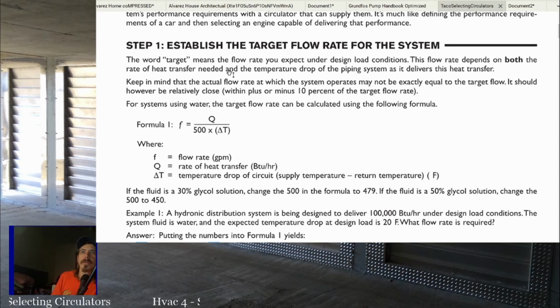All right, so the target is the flow rate you'll expect under design load conditions. The flow rate depends on both the rate of heat transfer needed and the temperature drop of the piping system as it delivers this heat transfer. Keep in mind the actual flow rate at which the system operates may not be exactly equal to the target flow. It should, however, be relatively close, within plus or minus 10% of the target flow rate.